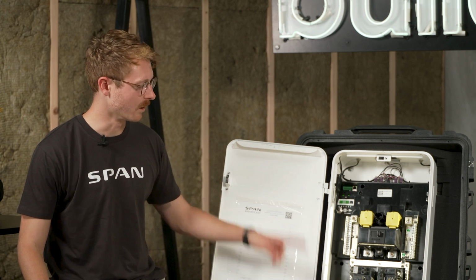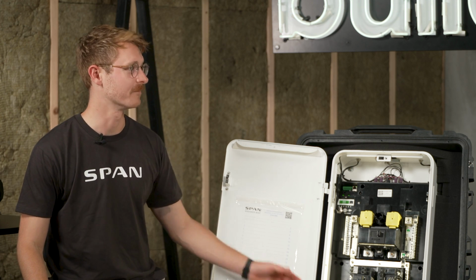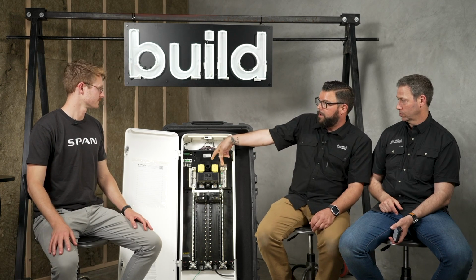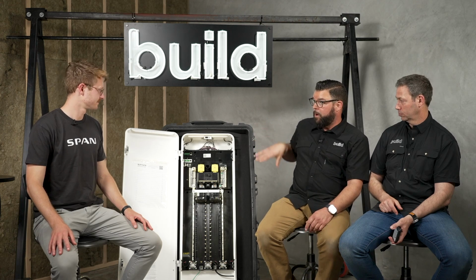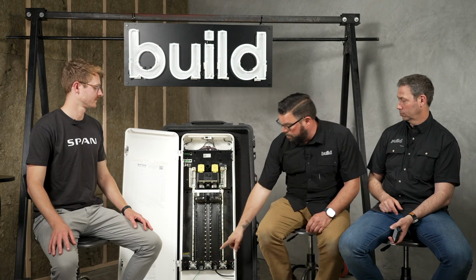And we also have 200 amp rated sub-feed lugs. So if you wanted to pass through to a series sub panel, that's possible. I could run 2 spans side by side, feed in 200 amps, and if I needed a little more and had extra money to spend and wanted a second panel, I can feed through my lugs into it.